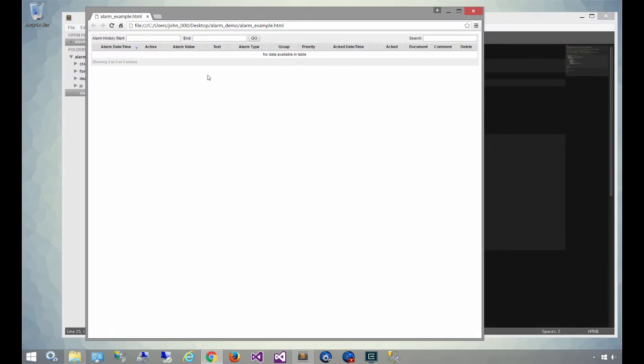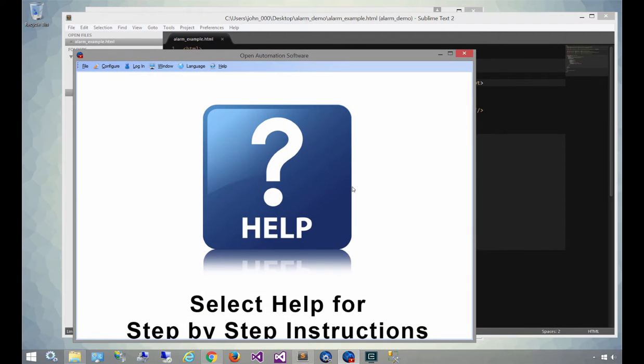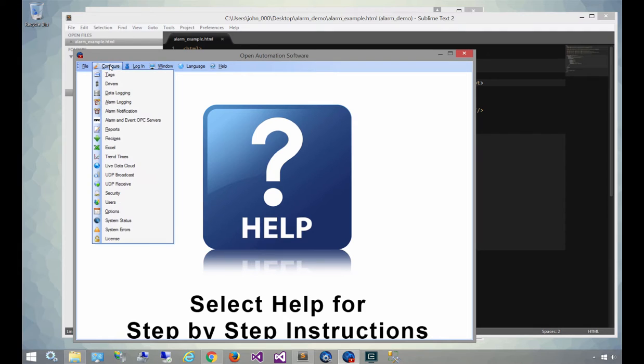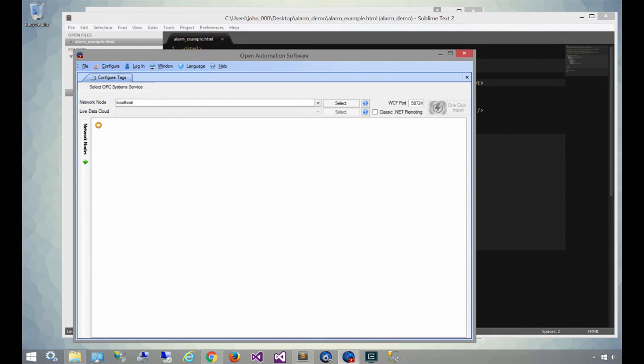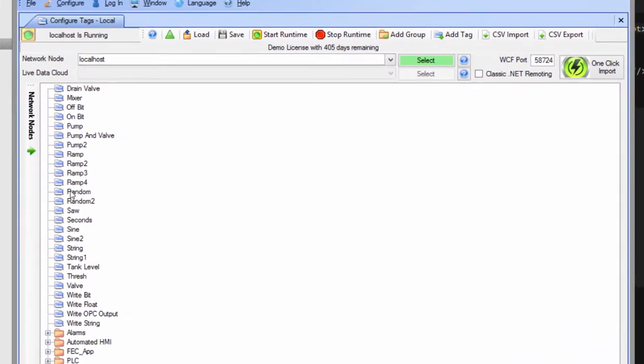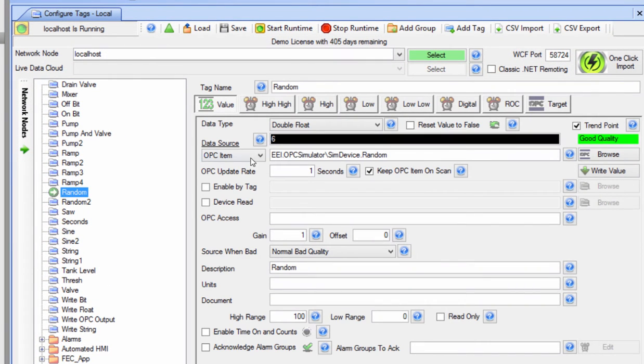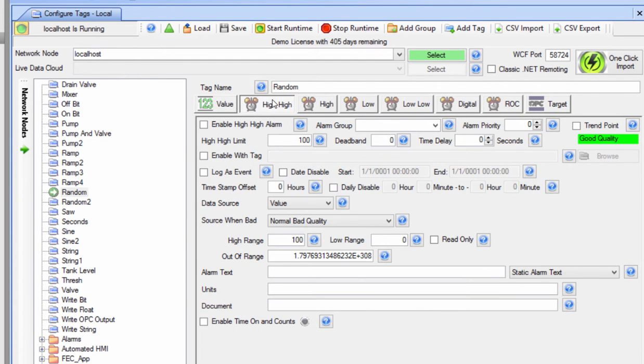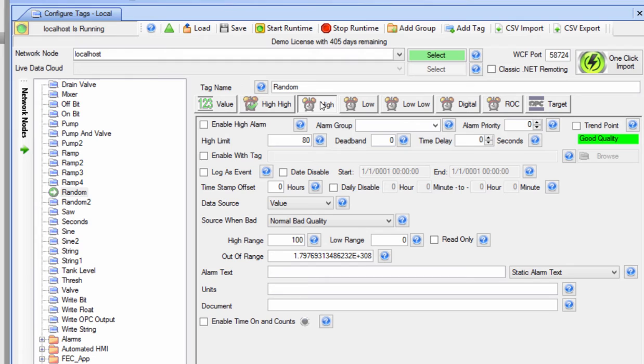So now I'm going to open up the alarm configuration so that we can add another type of alarm group, and we'll add that to our filter. When I select configure tags, we'll select the local host, and I'm going to select the random tag, and I'm going to add these alarms on that tag to the random alarm group. I'm going to do that for all of the random tag's alarms, including high high, high, low low, and low, enabling them as I go.